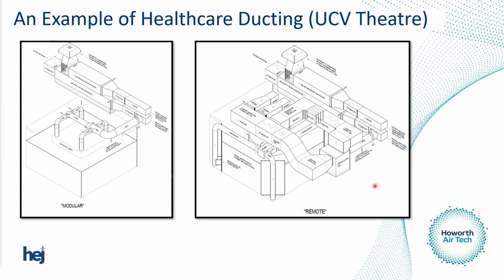So if you keep that in mind, obviously we've got the 10 times the diameter of the duct off the bend, so it'd be very difficult to take a traverse on that type of ductwork arrangement. And also you have the issue of measuring the recirc air. So these are low-level extracts from the operating theatre. These feed back into the system. There's additional components up there. We've got an attenuator, a cooling coil, the filtration sits above the canopy. And the reason that I'm showing you this is because you need to be aware of that when you're designing the ventilation system. You need to consider how you're going to get traverse to it, how we're going to clinically work out the air change rate for the operating theatre, and make sure that it's adequate and repeatable.